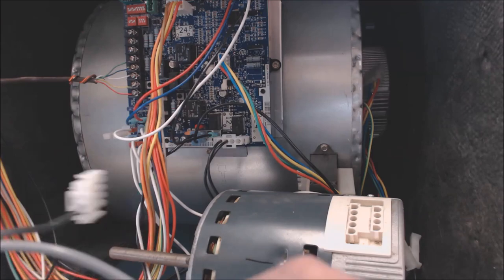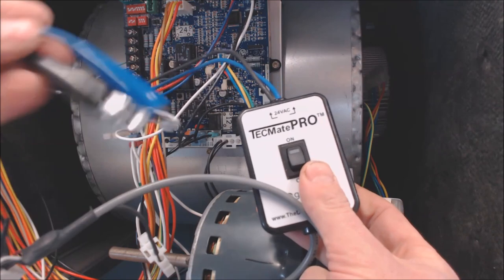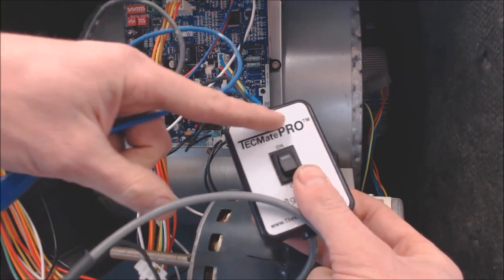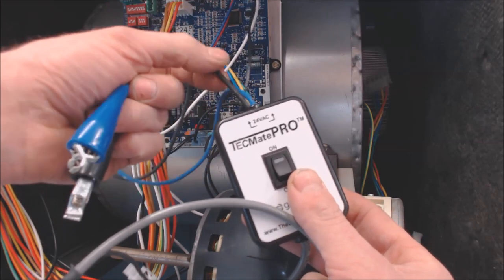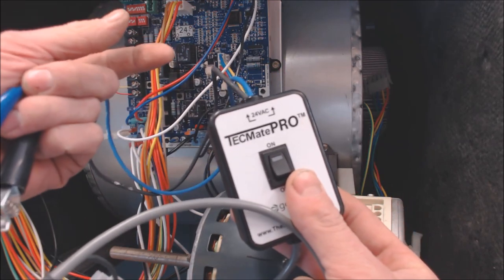Now, the other thing I want to mention, on this TECMate Pro, you are just connecting these two wires onto the control board, and it says 24 volts. It doesn't even tell you if you need to put this one on the hot and this one on the common. So really, I'm going to tell you, it actually does not matter.